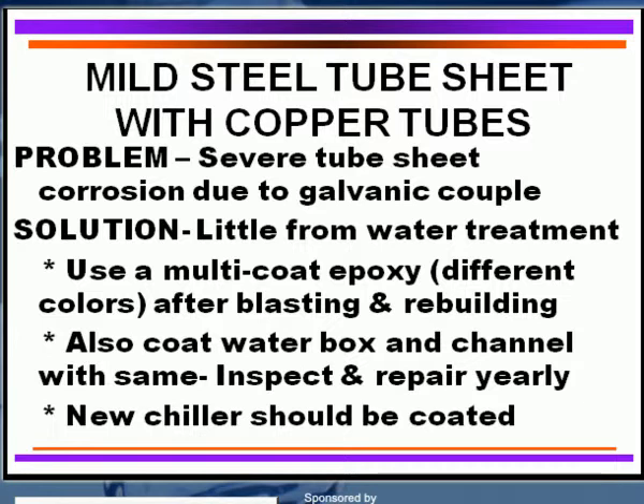What you need to do is go with a cleaning and sandblasting, rebuilding the surface, and then applying a multi-coat epoxy on that surface to protect it against the corrosive nature of the water. Why do we use a multi-coat epoxy with different colors? Well, if you use different colors, you can identify any voids that may have occurred in the first coating. I frequently like to have 3 coatings, 3 different layers of 3 different colors, and that works out very well. Be sure you also coat the water box and the channel while you're doing the same thing, because these contribute, of course, mild steel, iron oxide if it's corroding.